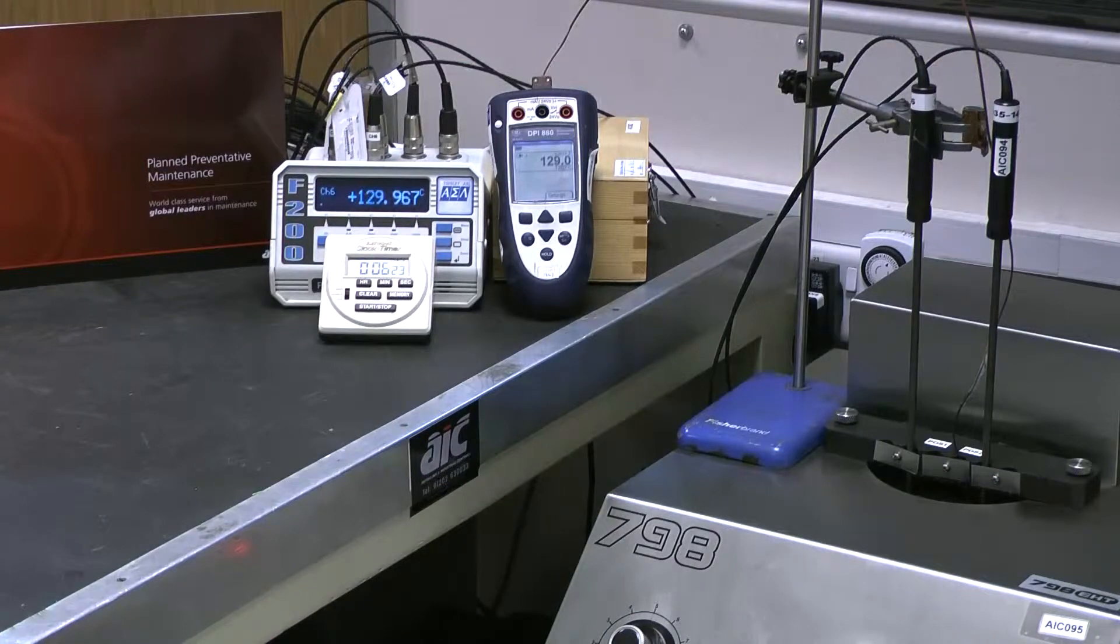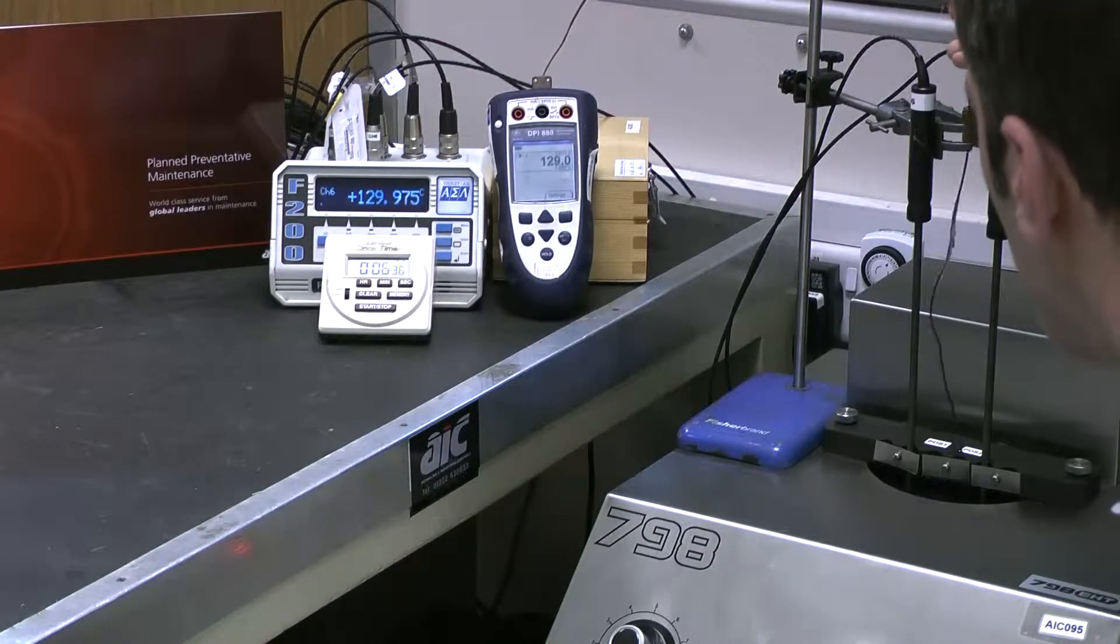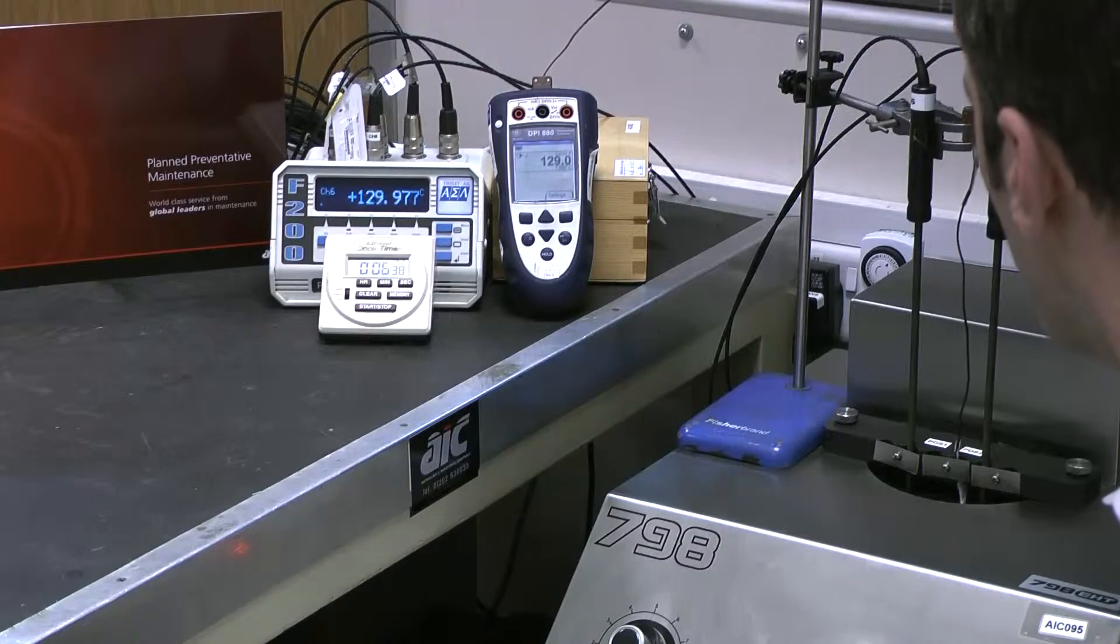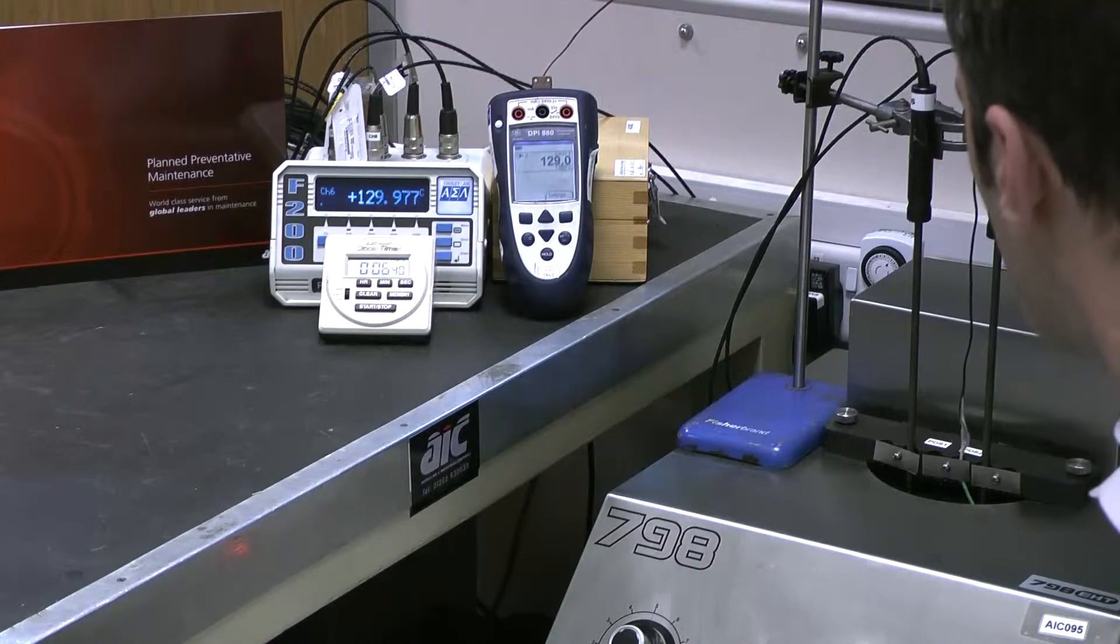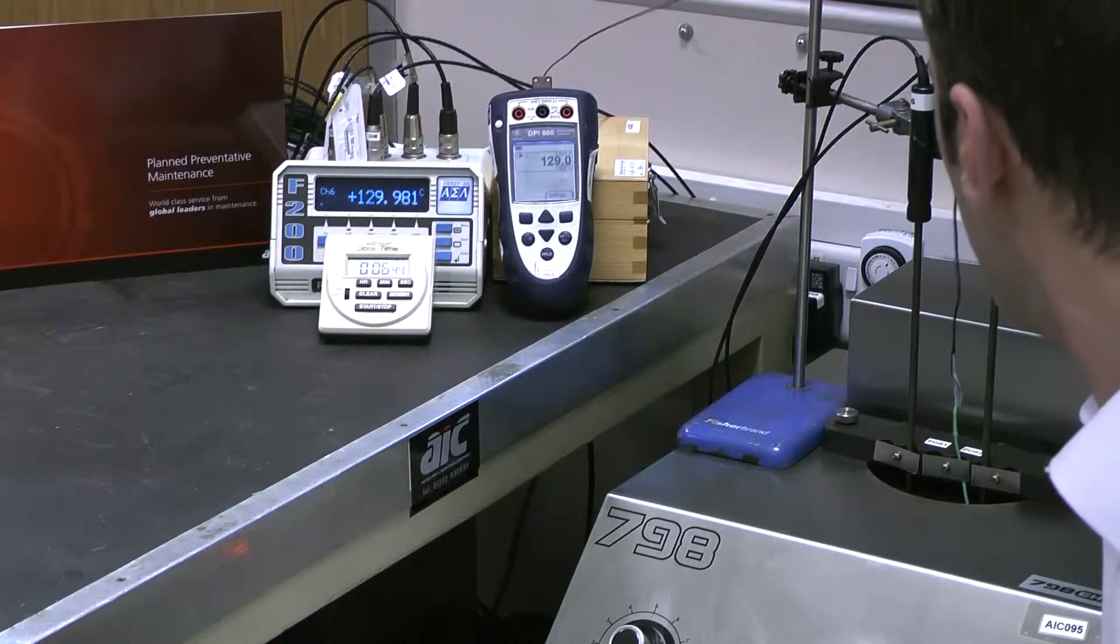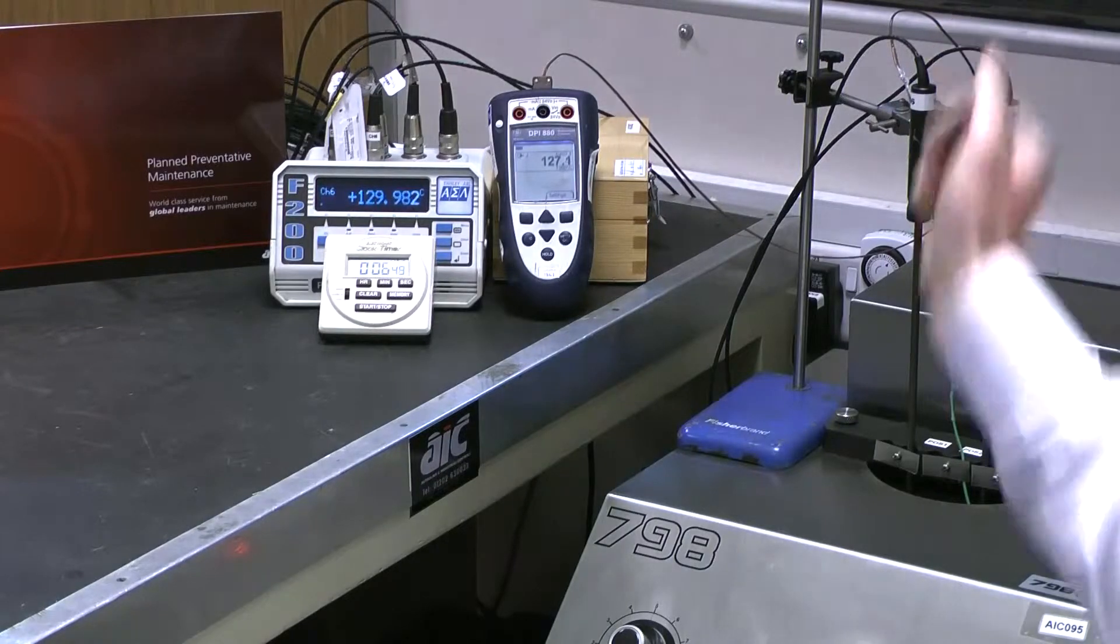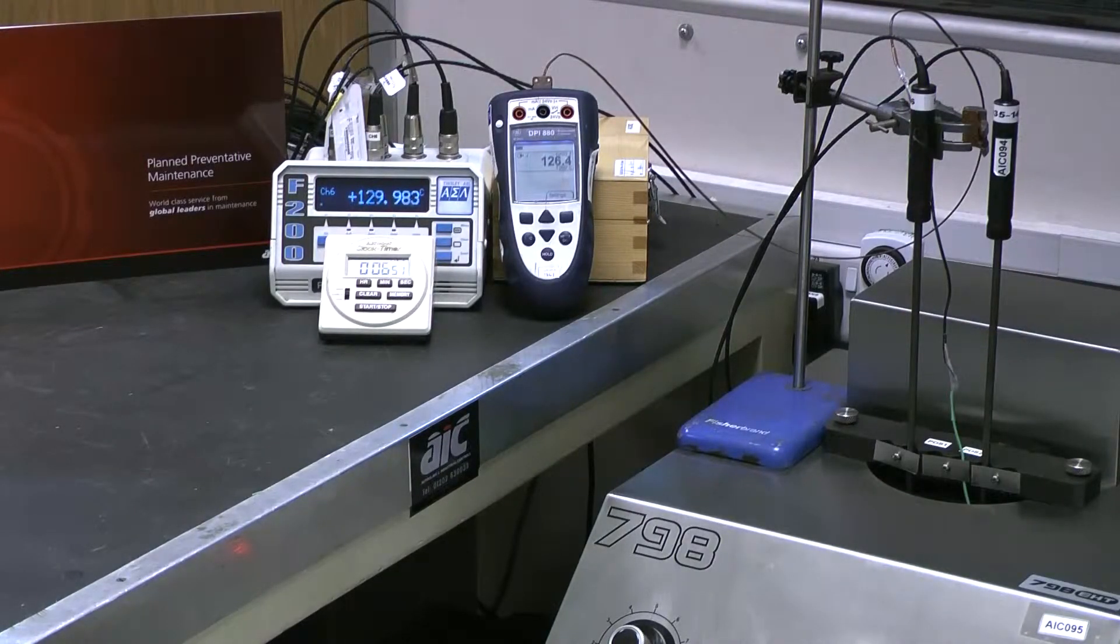So it's all about where the character of the cable where it experiences the temperature gradient. So just to illustrate the point a little further, we pull the thermocouple further, and it's no longer Type J, but Type K in the area of the temperature gradient. You can see that coming out of the tank down there.